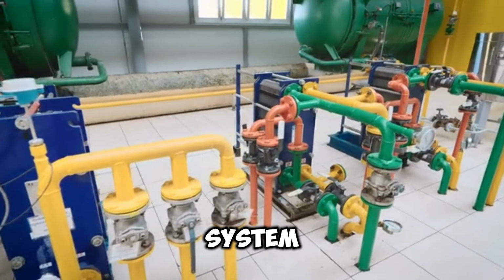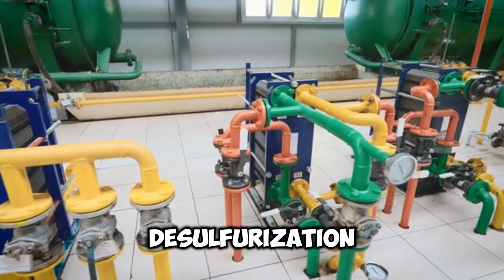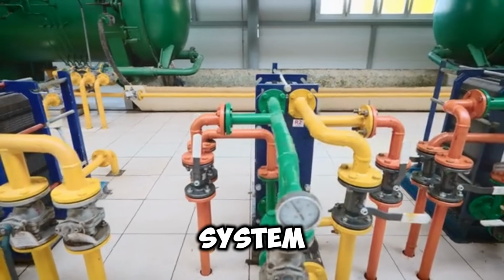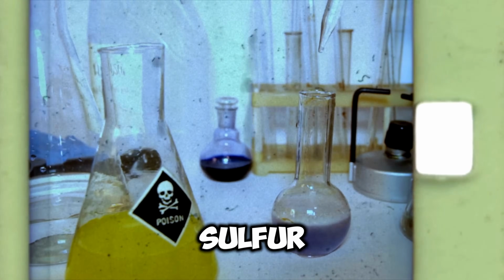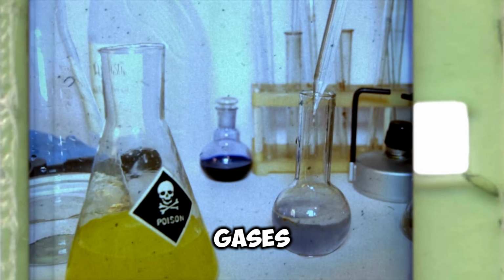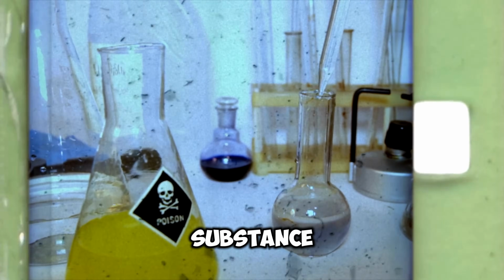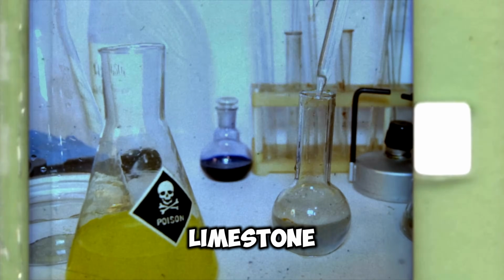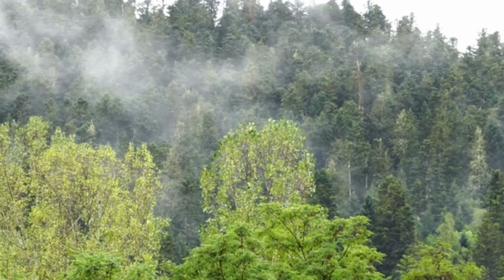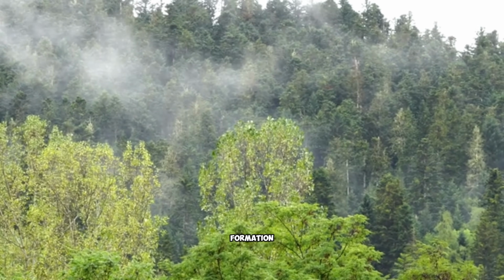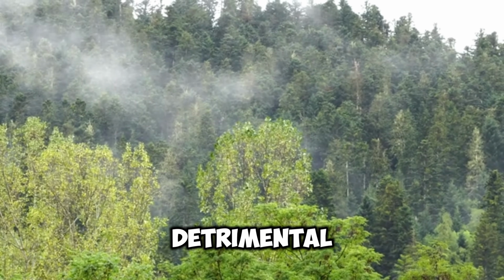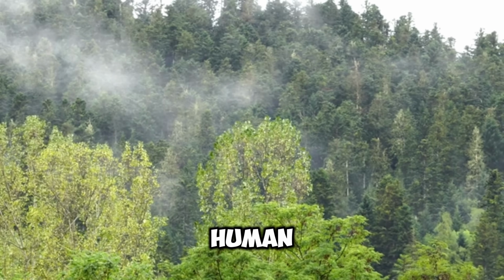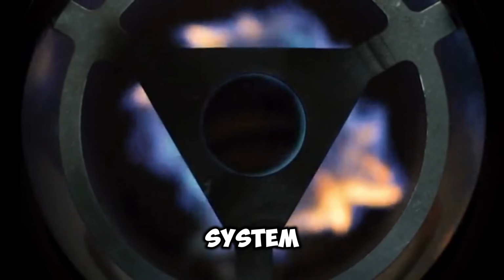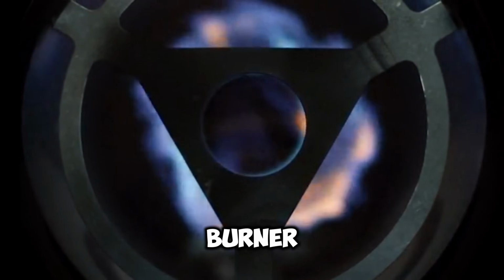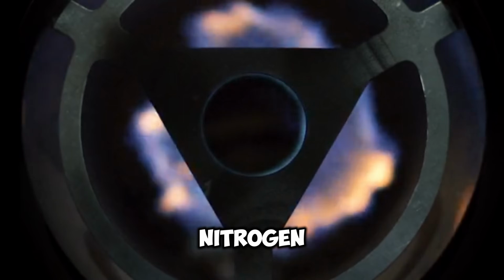One crucial system is the flue gas desulfurization, also known as the scrubber system. This system removes sulfur dioxide from the exhaust gases by reacting them with a chemical substance, typically lime or limestone. By removing sulfur dioxide, the plant significantly reduces the formation of acid rain, which can have detrimental effects on the environment and human health. Another system in place is the low NOx burner, which is designed to reduce nitrogen oxide emissions during the combustion process.